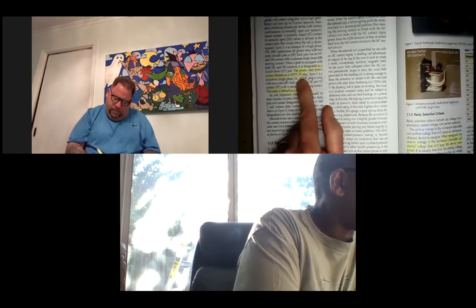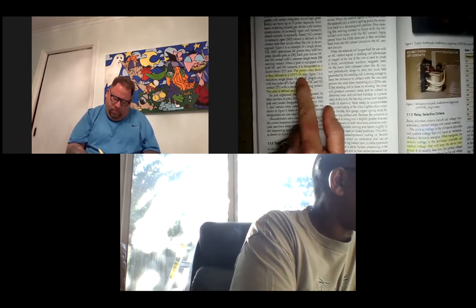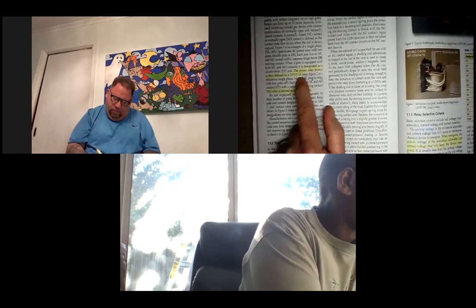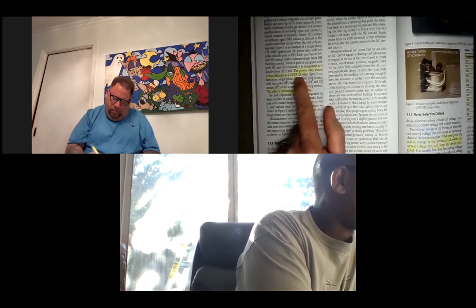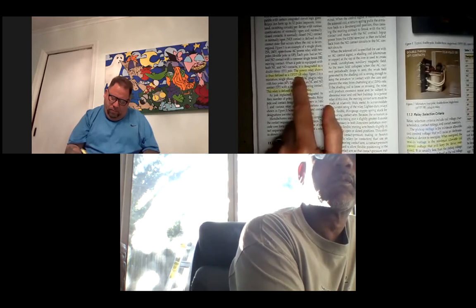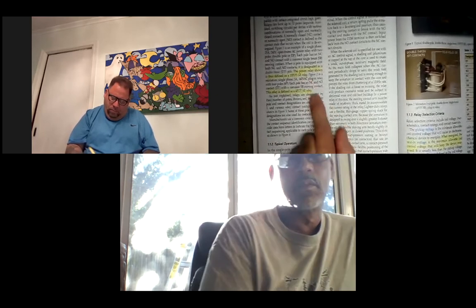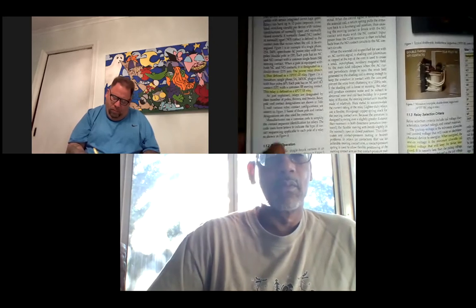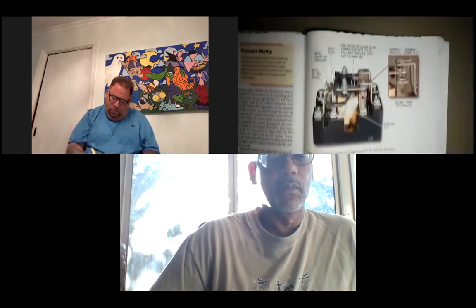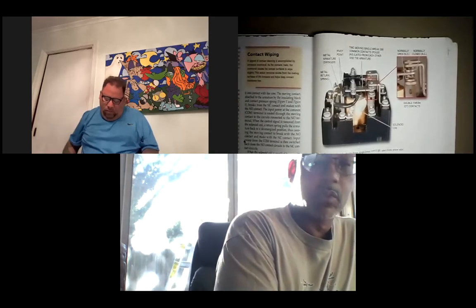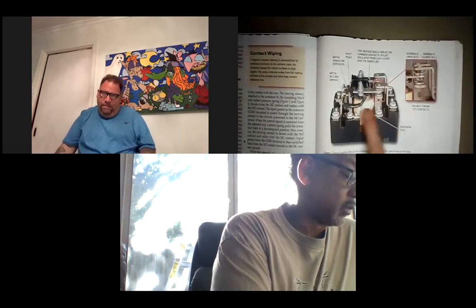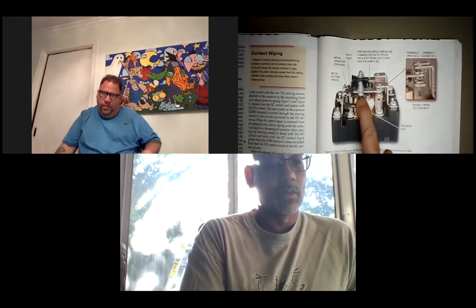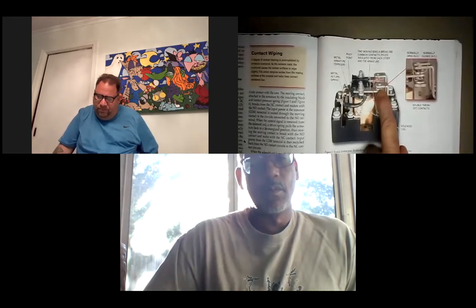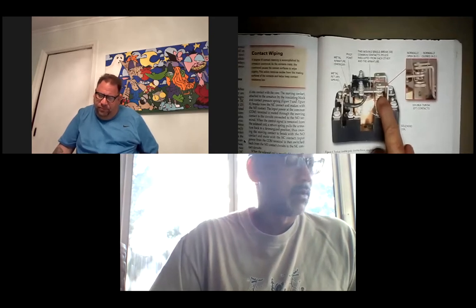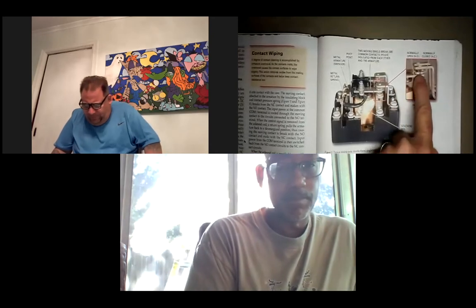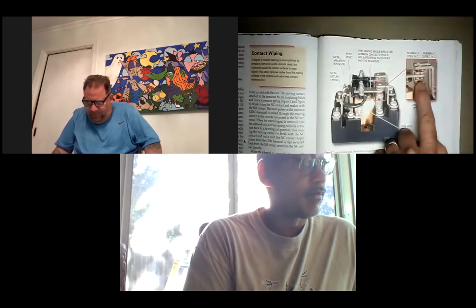A 3-way switch is a double throw switch. It can either be connected to one traveler or it can be connected to the other traveler. That's double throw. And then single break means that it's only breaking at one point. And we'll see a drawing or a picture of that, and we'll talk about single break. Here is an example of a single break. It's pivoting from one point, and on the other side, it's movable. So the make and break is only happening on one side.